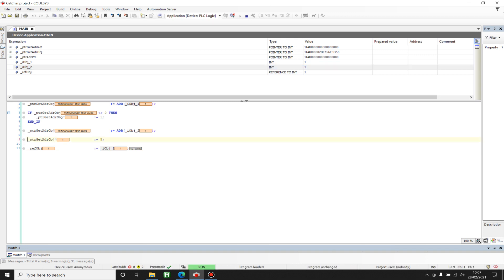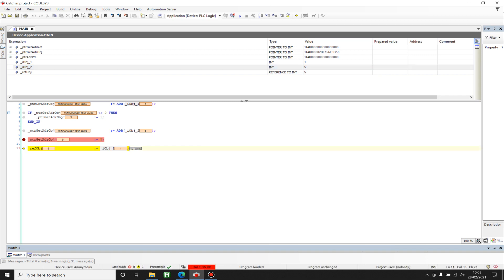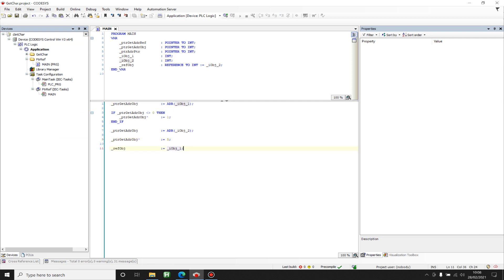Object 2 has the value 5. I will make a breakpoint so you can see that. As you can see, object 2 and the reference have the value 5, but in the next row we are assigning 1 to the reference, so because they share the same address, object 2 changes as well — both become 1. Before using a reference, you should make a special Codesys check using '__ISVALIDREF' and then use it only if valid.